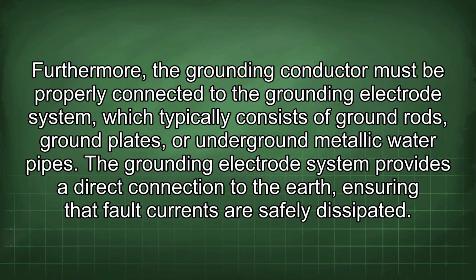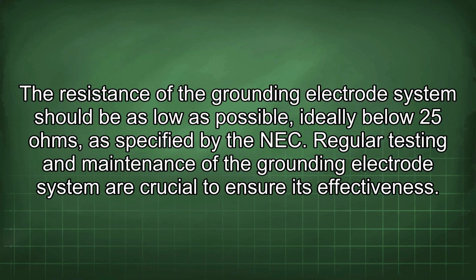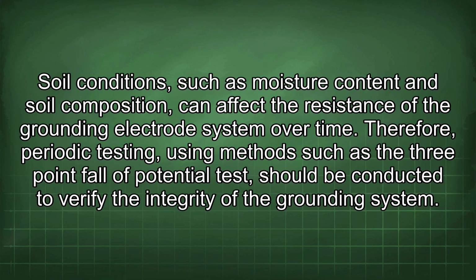Furthermore, the grounding conductor must be properly connected to the grounding electrode system, which typically consists of ground rods, ground plates, or underground metallic water pipes. The grounding electrode system provides a direct connection to the earth, ensuring that fault currents are safely dissipated. The resistance of the grounding electrode system should be as low as possible, ideally below 25 ohms, as specified by the NEC. Regular testing and maintenance of the grounding electrode system are crucial to ensure its effectiveness. Soil conditions such as moisture content and soil composition can affect the resistance of the grounding electrode system over time.